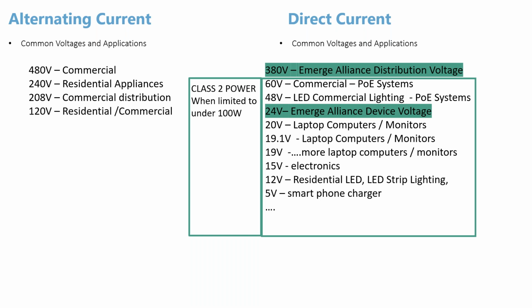The circuits using voltages greater than 50 volts are called line voltages, sometimes class one circuits, that are not safe to operate live, whereas the circuits using voltages less than 50 volts are called class two circuits. These class two circuits, limited to under 100 watts, are safe to touch. And this presents a big opportunity for savings by not needing high-skilled labor, since they're able to work on them live. So, you know, 50 volts is not going to kill you.